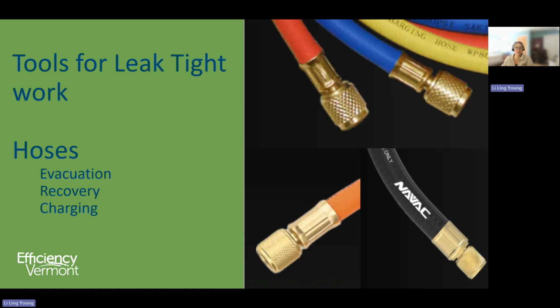When you have to use hoses, like for recovery, it's best to use a hose with as small an interior volume as possible. That keeps the refrigerant loss to a minimum. But there's also a big benefit to large diameter hoses, both for recovery and evacuation. A large hose makes the process go faster.